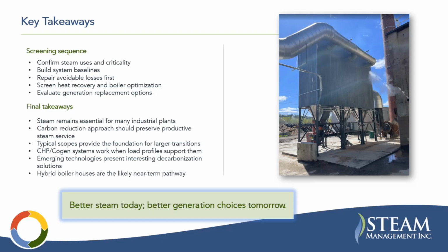For existing plants that do not have full steam metering, what minimum metering package do you recommend to establish a credible baseline for steam savings, boiler efficiency, condensate recovery, and carbon reduction? That's different for different plants. And I do have some suggestions on that slide. In my mind, I would probably see what's available and do a heat and mass balance and see what needs to be metered. And then those recommendations are often kind of custom site by site.